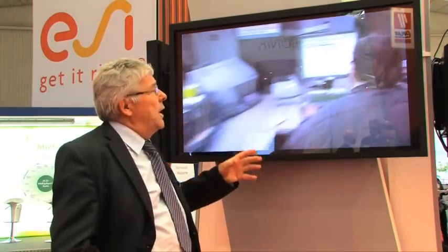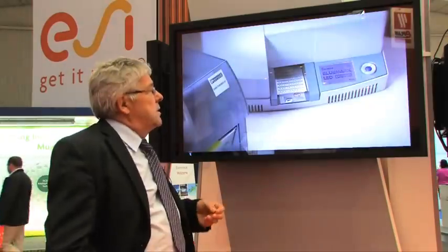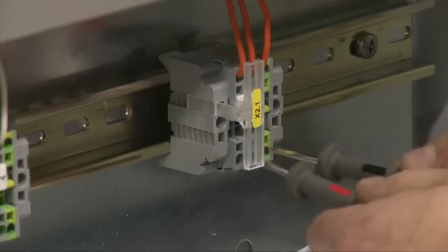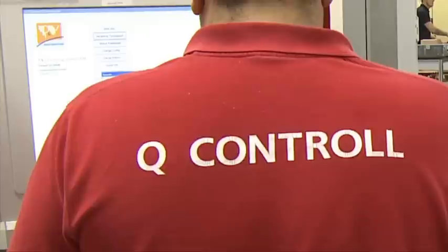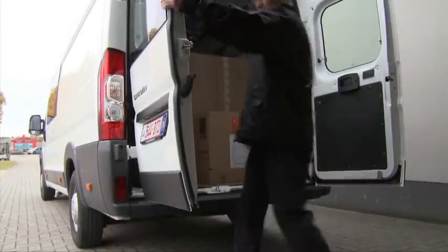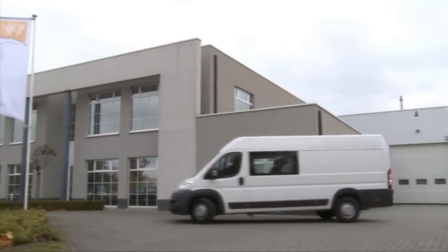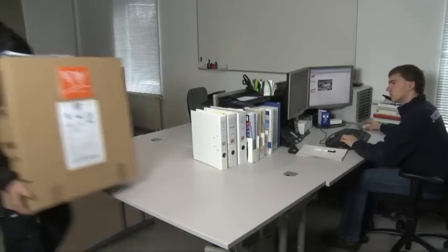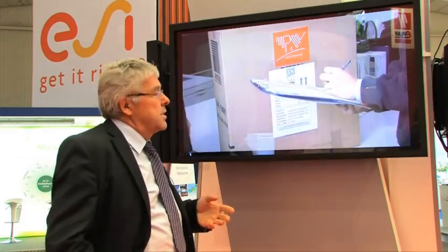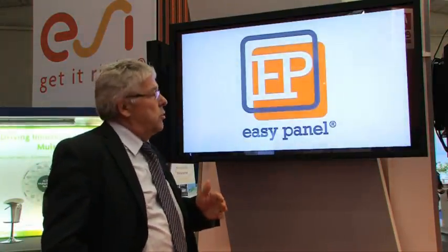When that's finished, labeling is also automatically created by EPLAN — the numbering, the engraved plates, and the full ID package are completed. There is always a final quality control by human beings. Our promise to customers is a delivery time of one week for distribution panels up to 125 amps, and two weeks for panels up to 630 amps. Our challenge to the installers was to cut the price and achieve a very short delivery time, and we have met that target with this solution.